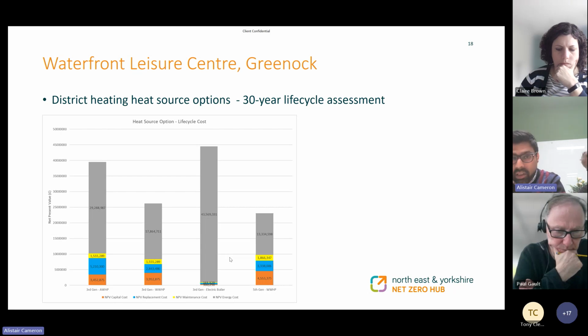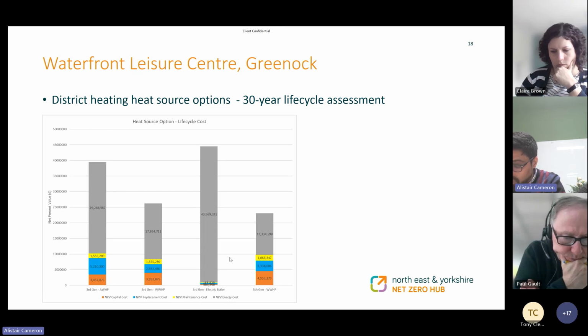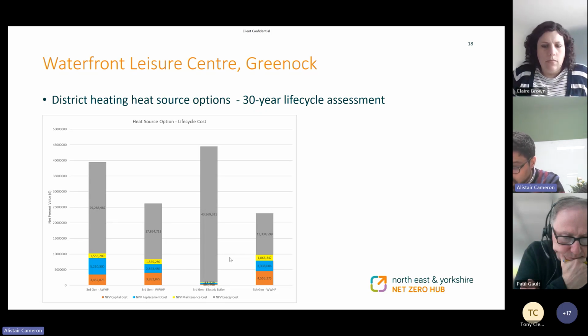So immediately you'll see that the electric boiler option is the cheapest in terms of capital cost, and the cheapest in terms of maintenance costs. However, the actual energy cost to operate is very, very high, and that makes it the most expensive over that 30-year period. So that one was discounted for that reason. It was just too expensive to operate and not economically viable for the council to service over that 30-year period in terms of their electrical bills.